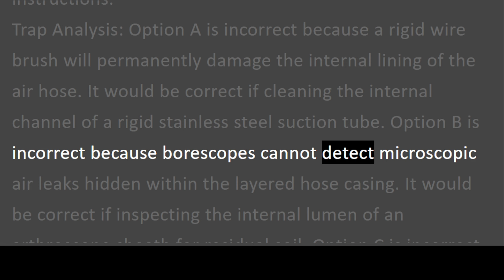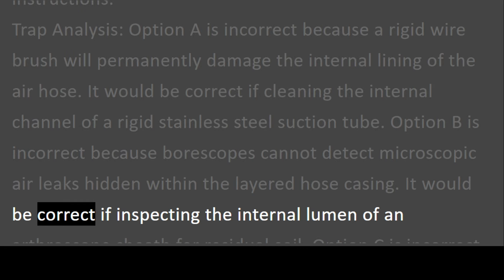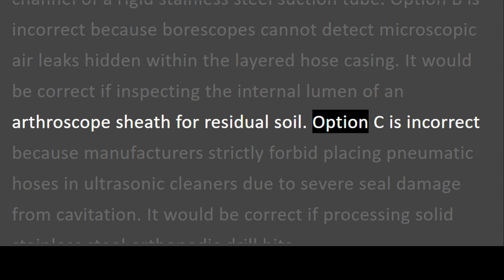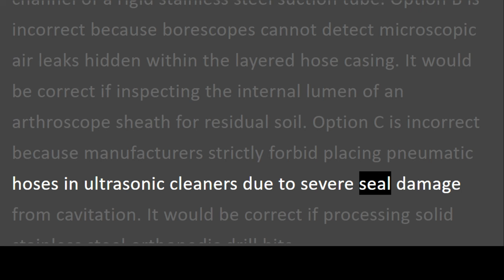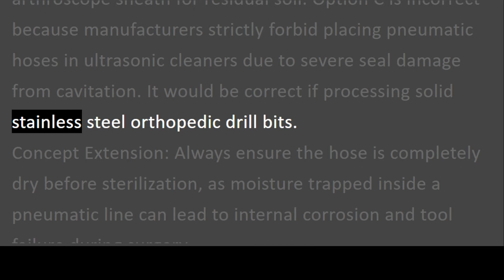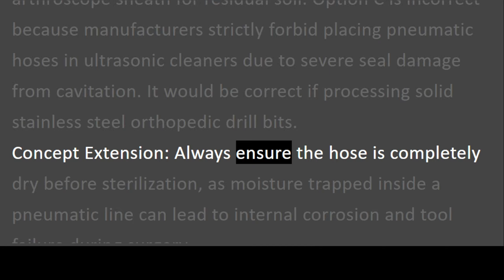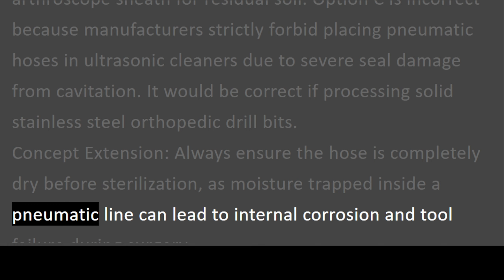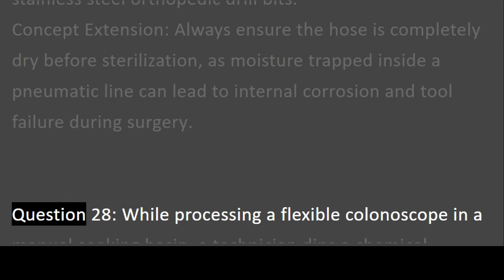Option B is incorrect because borescopes cannot detect microscopic air leaks hidden within the layered hose casing. It would be correct if inspecting the internal lumen of an arthroscope sheath for residual soil. Option C is incorrect because manufacturers strictly forbid placing pneumatic hoses in ultrasonic cleaners due to severe seal damage from cavitation. It would be correct if processing solid stainless steel orthopedic drill bits. Concept extension: always ensure the hose is completely dry before sterilization, as moisture trapped inside a pneumatic line can lead to internal corrosion and tool failure during surgery.